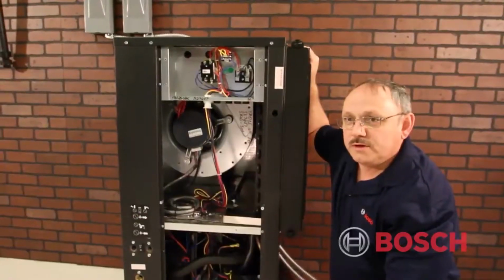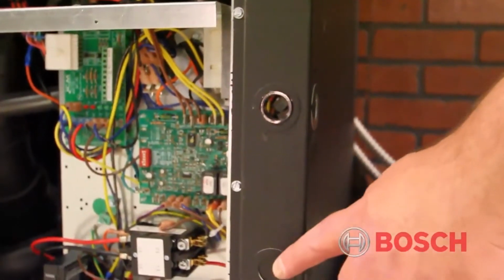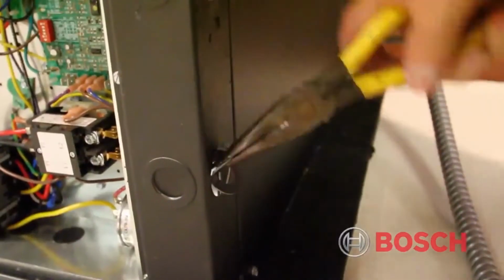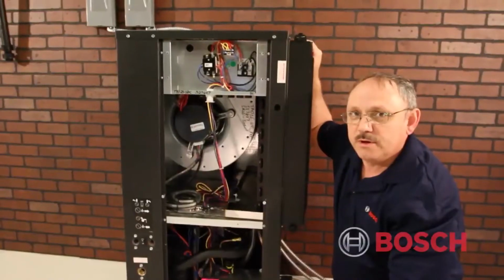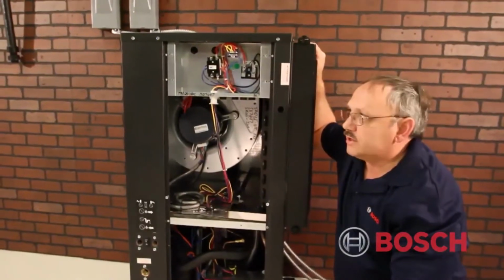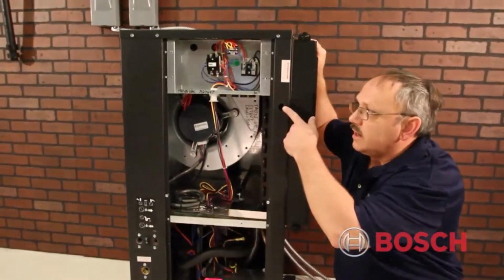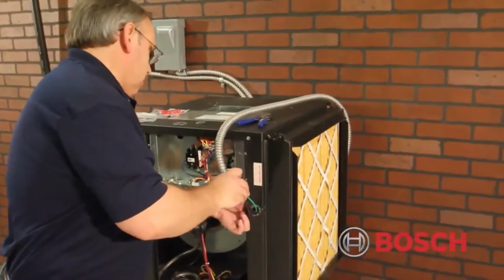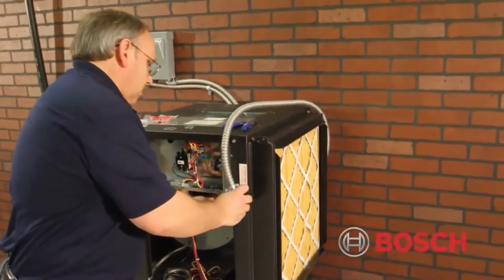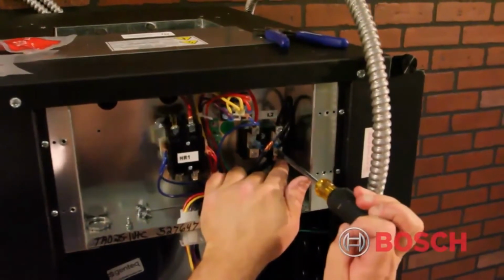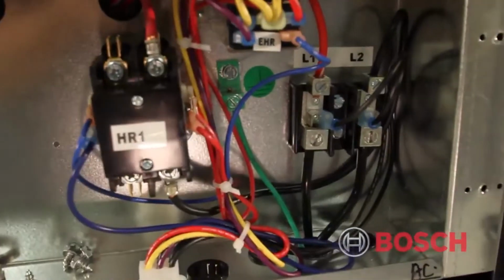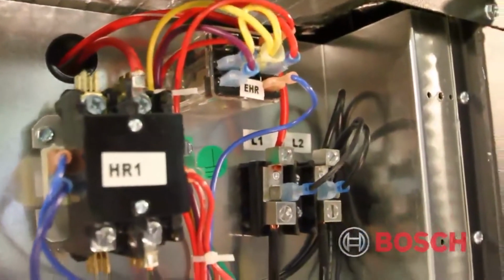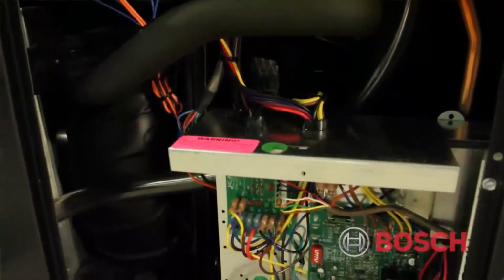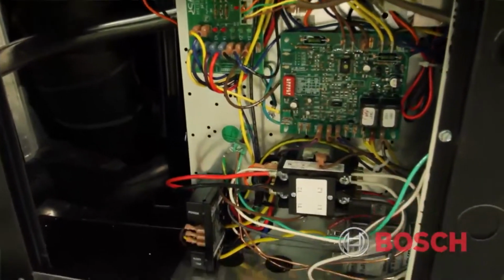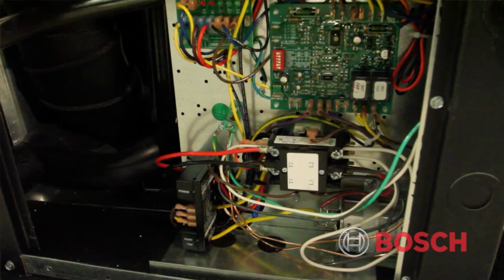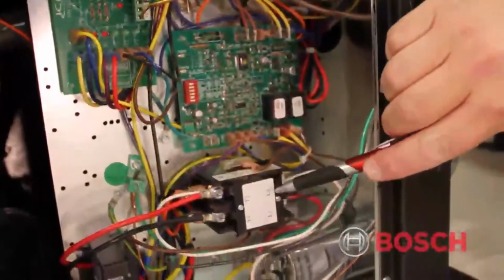There are several electrical openings on the right side of the cabinet. There are concentric openings so that you can make your high and low voltage connections to the equipment. For your heater connections, there is a knockout located on the top of the cabinet. It will give you access to run your wire into the electrical box for the electric heaters. There's a terminal block located in that box for you to make those connections. And connections for your compressor contactor are located down in the electrical compartment in the lower access panel. You'll make those connections to the compressor contactor at terminals L1 and L2.